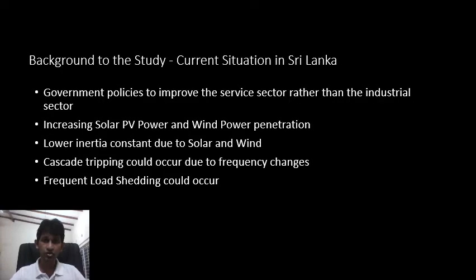Therefore, when solar and wind are installed more rapidly in the day-to-day proceedings, as time goes on, that means we are facing a less inertia system. We are moving towards a less inertia system. That means frequent under frequency load shedding could occur.